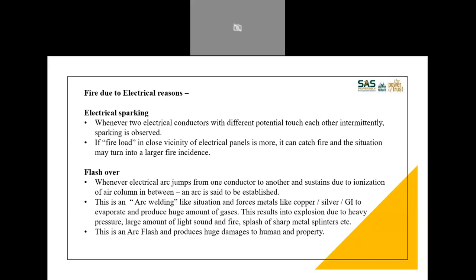So because of high energy in the initial jump, if the air gets ionized between these two conductors, then the arc is established. The situation is something like arc welding. Whatever happens in arc welding, the same thing happens here. All of us know that an arc welding transformer generally is of only 25 or 30 kVA rating. This is also large I am talking about. It could be even 10 kVA, it could be even 5 kVA as well.